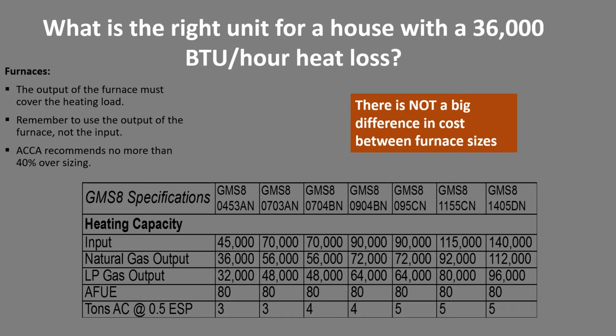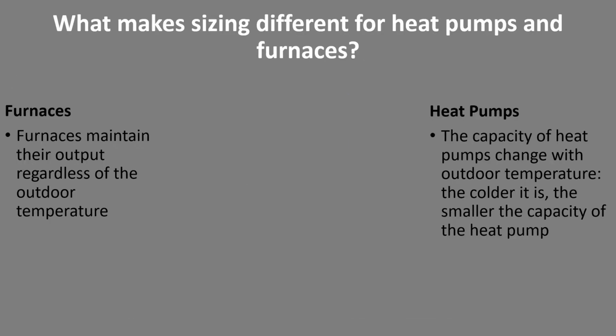So real quickly here, what would be the right size unit for a house with 36,000 BTU per hour worth of heat loss? There's not a big difference in cost in furnaces, so upsizing doesn't cost the customer too much money. But if we had 36K here, we see this 45K furnace here. The output's 36, so we'd probably say, I don't know if I want to be on the edge here. I think going up one size would be perfectly acceptable.